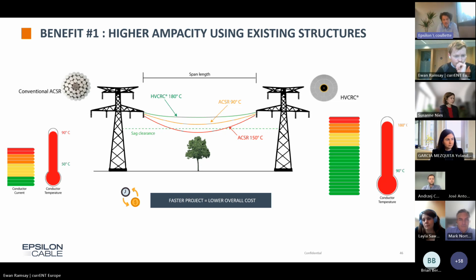This is a clear benefit that makes it possible to enter into reconductoring projects to double the ampacity of a line without endless impact studies, without bothering about right-of-way issues, and by keeping construction work lead time under control. From our experience, it's possible to go from project awarding to delivery and first installation of the conductor onto existing lines with a global cycle of less than one year. Less than one year to double the ampacity of lines - that is clearly unbeatable.